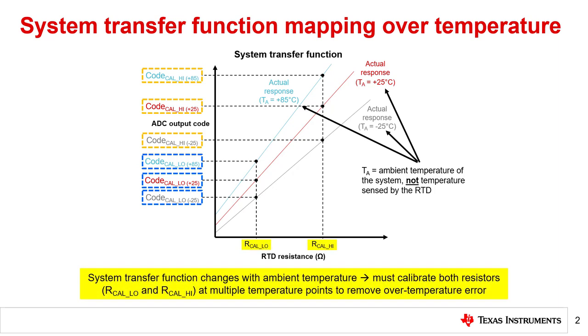Since it is not possible to calibrate out the error at every individual temperature, we need to choose a few calibration temperatures and assume the temperature error is linear between these points. Importantly, we still use the same calibrated resistances, RCAL low and RCAL high, to generate these additional ADC codes.